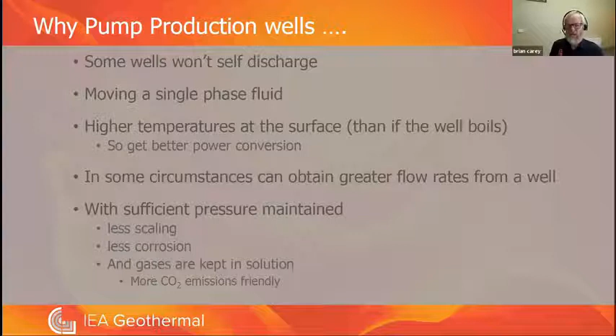For wells that won't self-discharge, you can use pumps to produce the fluids. Advantages of pumps include moving a single-phase fluid to the surface, and achieving higher surface temperatures than if the well boils, since boiling causes temperature to decrease up the wellbore. This means better power conversion at the surface when pumping wells, and in some cases greater flow rates. With sufficient pressure maintained in the facilities, you also get less scaling, less corrosion, and gases stay in solution, giving a more CO2-friendly emissions profile.